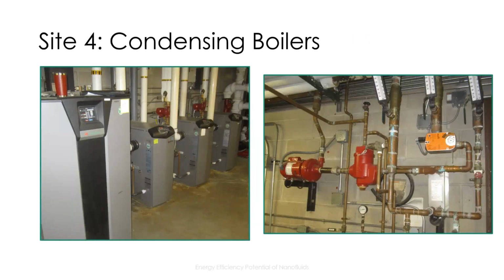The fourth site involved a series of condensing hot water boilers at a rehabilitation facility. This system serves not only some HVAC coils, some heating coils, but also a series of subloops that serve a pool heating system, general domestic hot water, as well as a snow melt system. So the primary hot water loop feeds all of these subloops via a series of heat exchangers.